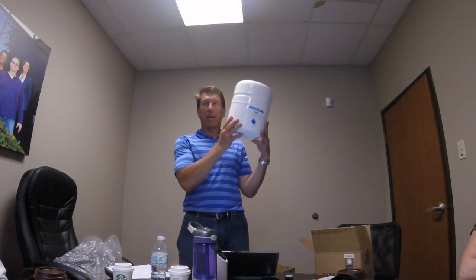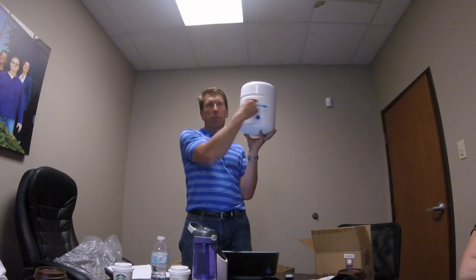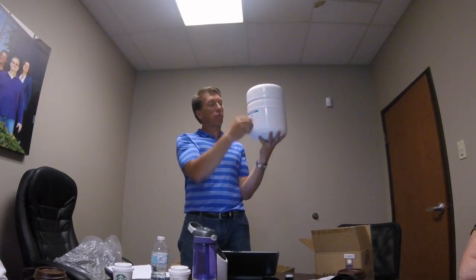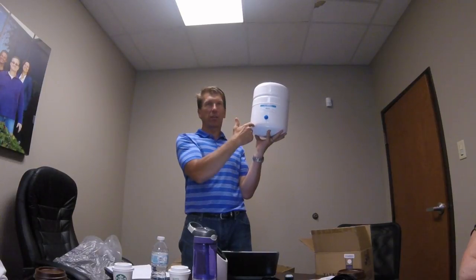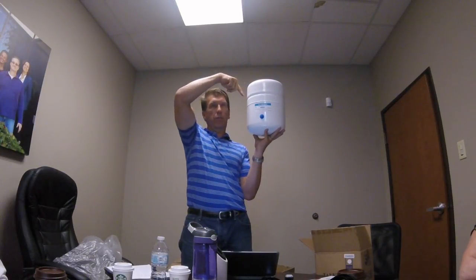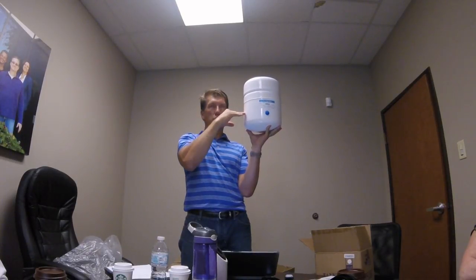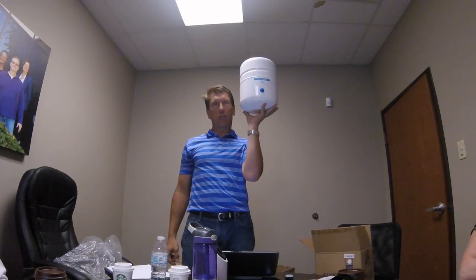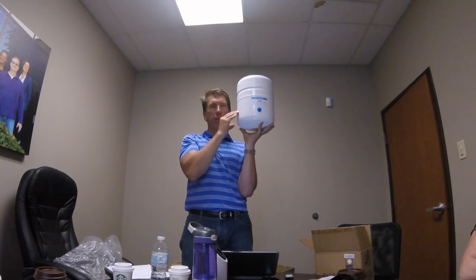Gallon tank. This is a diaphragm tank. In the middle, it's welded together. There's a rubber diaphragm in between the two sides. On one side is air, which is pressurized right here. Got a regular little Schrader valve on here that you pressurize up. It's air on this side. We bring in water on the other side. Water pushes on the diaphragm and then pushes that diaphragm down until it equalizes pressure on both sides. These are pre-charged at about 6 psi of air pressure. So water comes in on this side, pushes that diaphragm down.